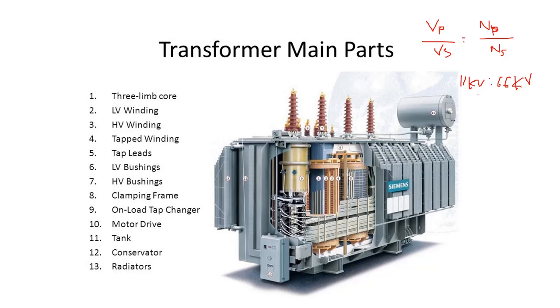But in a power system, depending on the load, you may have some voltage drop over the line, and at the end of the line you may have a situation where the voltage is much below the ideal voltage level it should have. For example, say this is our 11 kilovolt bus, and from here you have a distribution line, and here you have a transformer connected. From this 11 kilovolt the transformer transforms to 400 volt line to line, or 230 volt phase to ground. So this is a three-phase line, and of course it has a neutral.